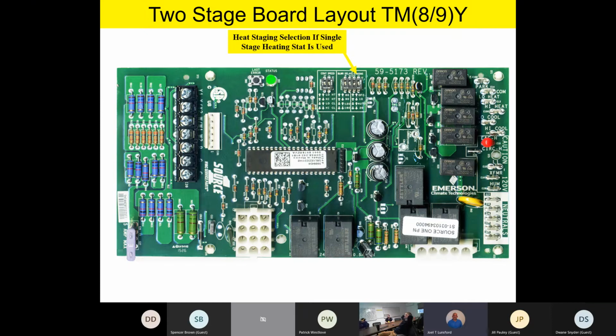Now, it should be noted, if both dip switches are in the off position, you get no staging beyond first stage. So this is important. If you're stuck with a single stage thermostat and those dip switches are in the off position, you'll never get out of first stage. However, you have a 10-minute option. If you have one dip switch up and one down, the one on the left up and the one on the right down, that gives you 10 minutes between first and second stage.